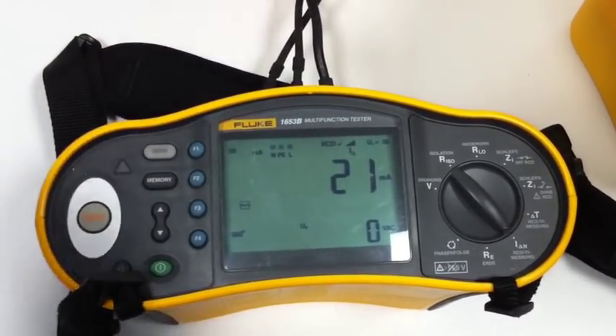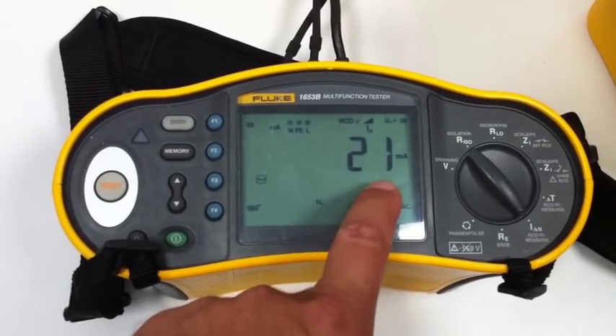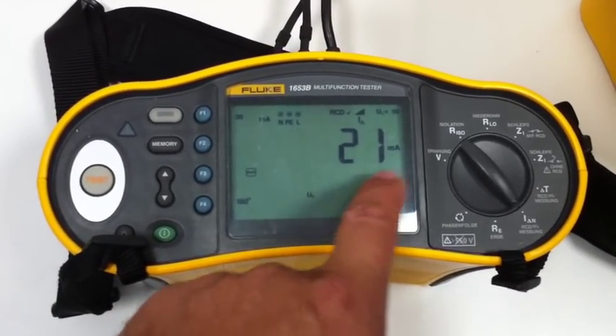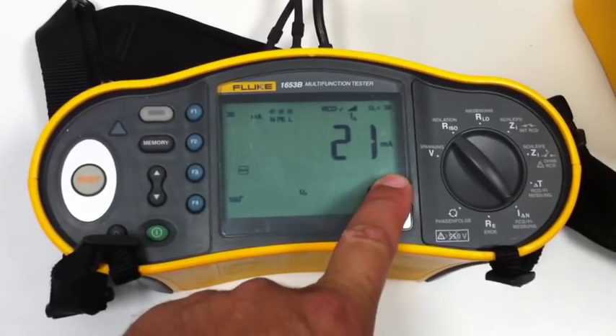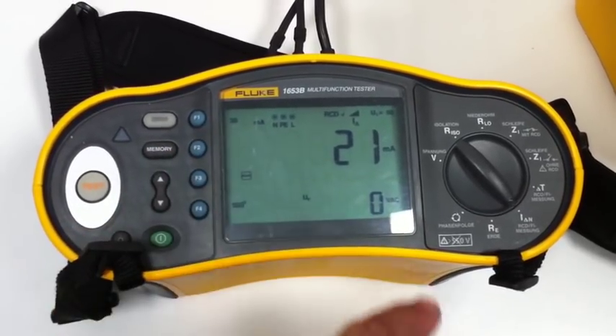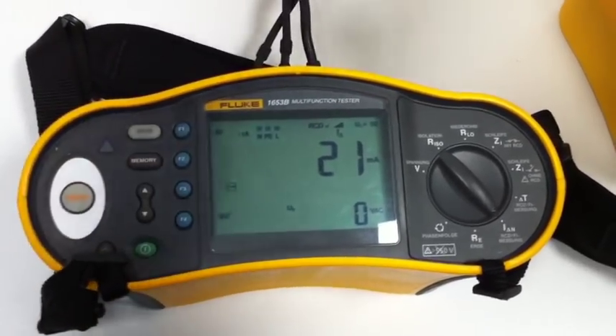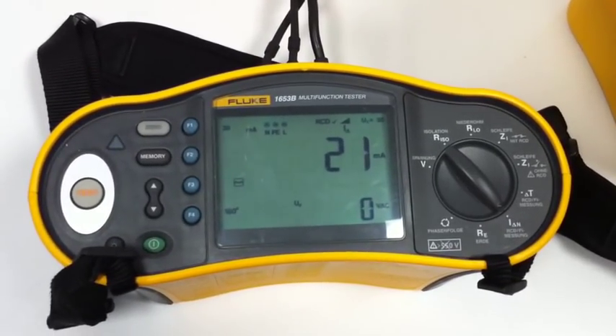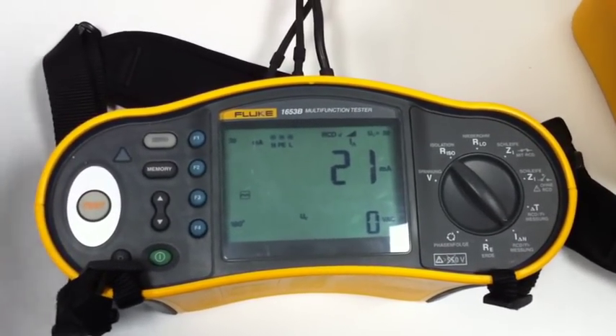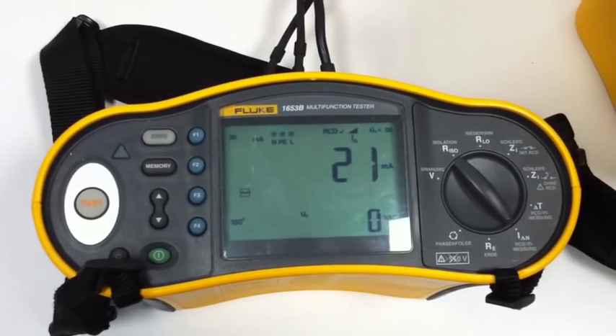You may have heard the click - it tripped when this meter added 21 milliamp to the circuit. That means for this 30 milliamp RCD, there's 9 milliamp leakage current in the circuit. This is quite normal, there's nothing wrong with that.